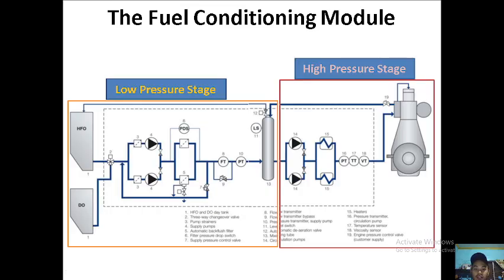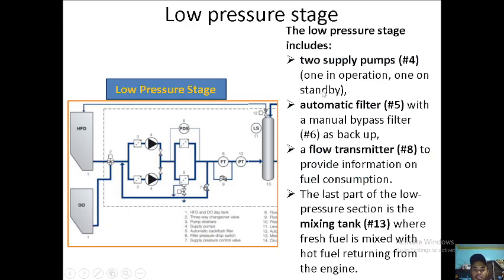This fuel conditioning module is divided into two stages, the low pressure stage and the high pressure stage. We will first discuss the low pressure stage, the equipment and the function. The low pressure stage includes two supply pumps here, number 4. One in operation and one on standby. If ever there is a problem on the operating pump, automatically the standby pump will start. Next we have the automatic filter, number 5, with a manual bypass filter, number 6, as a backup. These are the parts of the low pressure stage.